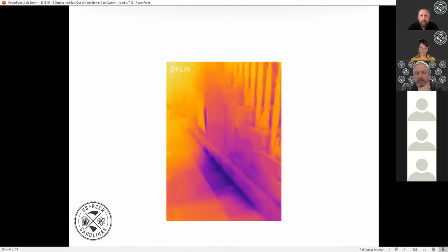There's a return on the first floor, shown in one of the crawl spaces later on. Part of that return coming up from the floor was using the floor joists as part of the airflow pathway, and it was super leaky. During the blower door test, we could see cold air coming up out of that crawl space, from around that return underneath the stairway.